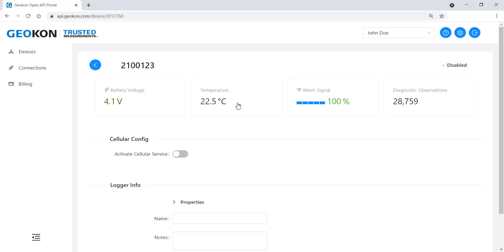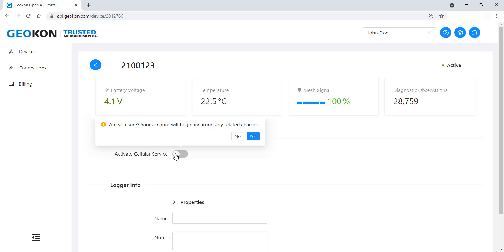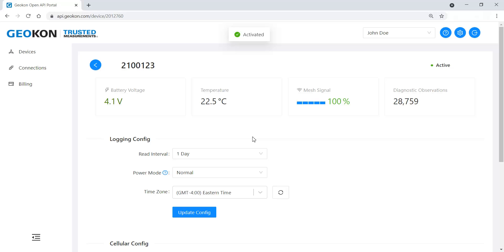Activate the cellular service to begin sending data to the portal. Once the service has been activated, charges will commence on the account. When utilizing a mesh network, only the cellular gateway needs to have the cellular service activated. The loggers do not. For model 8920 series cellular loggers, each logger needs to be activated individually.